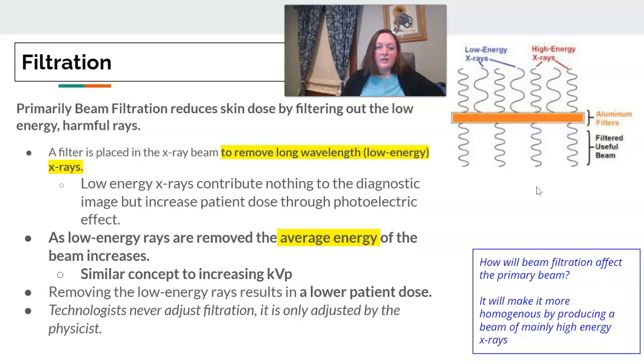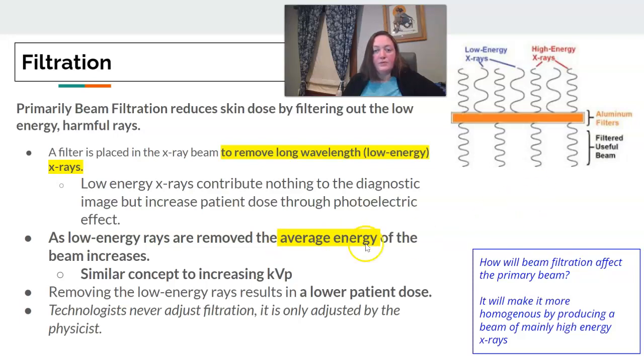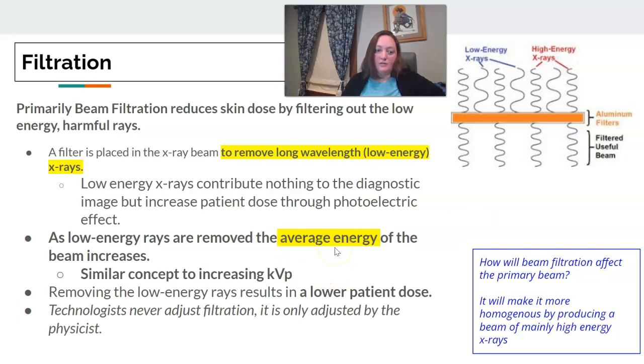The low-energy X-rays contribute nothing to the image — they simply increase patient dose because they're more easily absorbed. When filtration removes those low-energy photons, the average energy of the beam increases. This is a similar concept to increasing your KVP: increase KVP, increase energy; increase filtration, you increase the average energy of the beam.